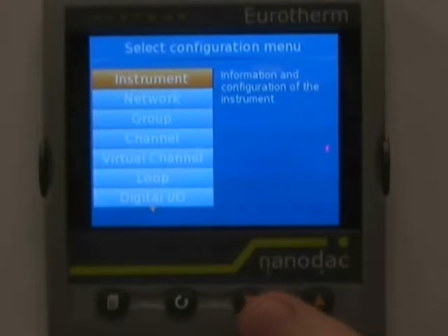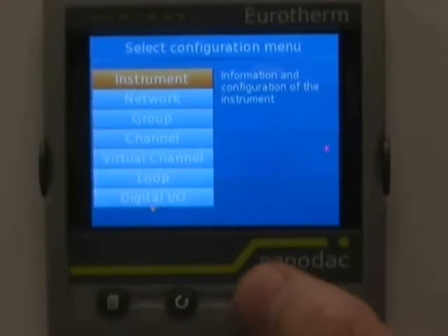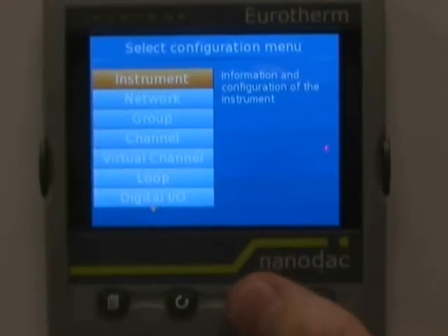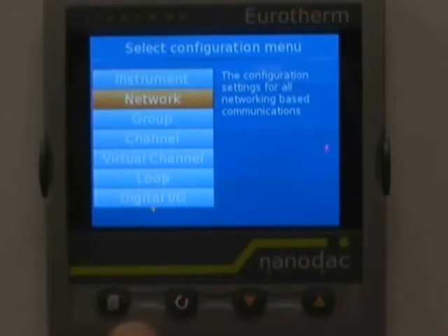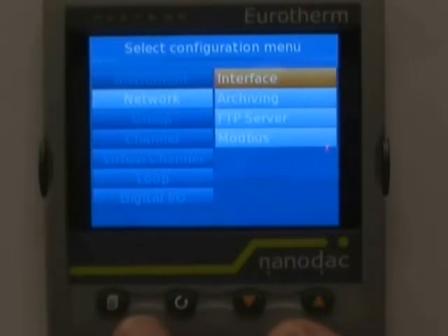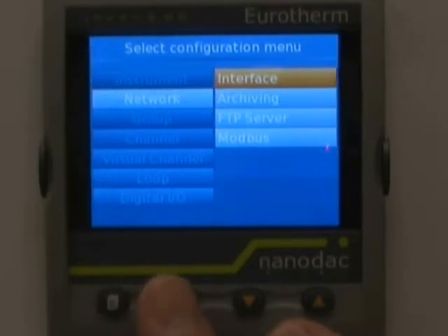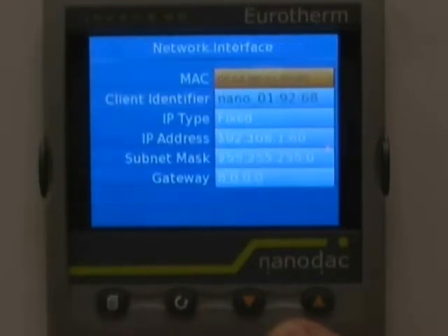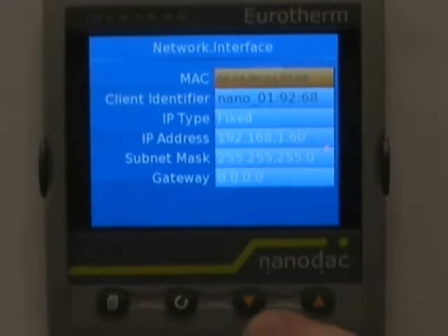Now, to change the IP address, hit the down arrow down to Network and hit the scroll key once — that brings up another sub-menu of Interface, Archiving, FTP Server, and Modbus. We want to go into Interface; hit the scroll key once and that will bring up the network interface information.